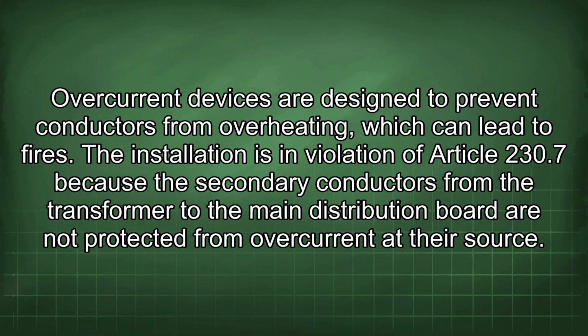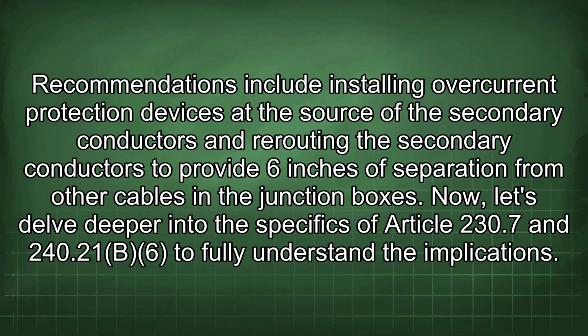The installation is a violation of Article 230.7 because the secondary conductors from the transformer to the main distribution board are not protected from overcurrent at their source. Recommendations include installing overcurrent protection devices at the source of the secondary conductors and routing the secondary conductors to provide 6 inches of separation from other cables in the junction boxes. Now, let's delve deeper into the specifics of Article 230.7 and 240.21(B)(6) to fully understand the implications.